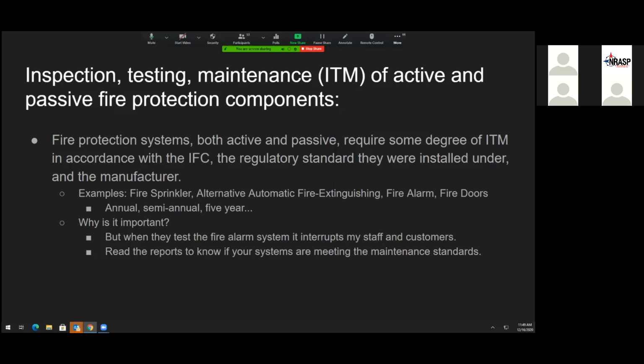Both active and passive fire protection systems require some degree of inspection, testing, and maintenance in accordance with the fire code, the regulatory standard in which they were installed, and the manufacturer. So for example, just regular wet pipe sprinkler systems, the basic testing requirements are an annual test requirement. They do have 5-year test requirements and other things as well, but at the basic minimum, it's an annual test requirement. Most of the alternative automatic fire extinguishing systems, such as clean agent and kitchen hood suppression systems, require a twice-a-year test. Fire alarms require annual tests, and as I said earlier, fire doors actually require annual tests as well. So make sure that your systems are being maintained as they should be, which also includes per the manufacturer.